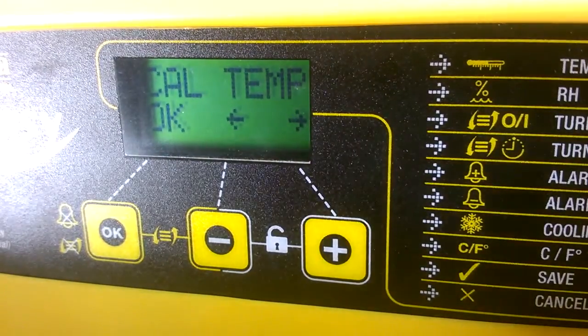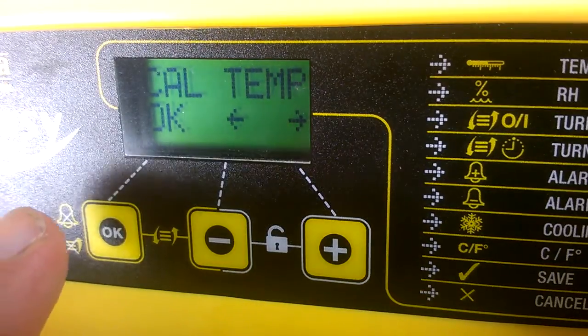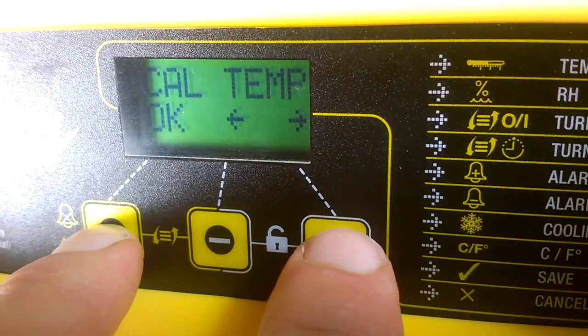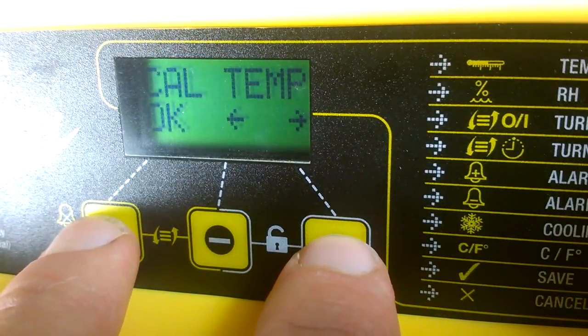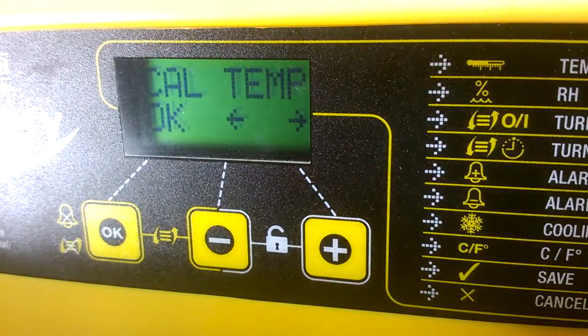Now, if you've got your thermometer set up on the tray, on a block, and the trays start turning, your thermometer will roll off and probably fall to the bottom of the machine and possibly break, possibly split the little mercury thread, which isn't actually mercury anymore, but the little thread that's in the thermometer. So either way, that's not something you want to happen. So remember, OK plus and the minus immediately afterwards to enter the calibration menu.